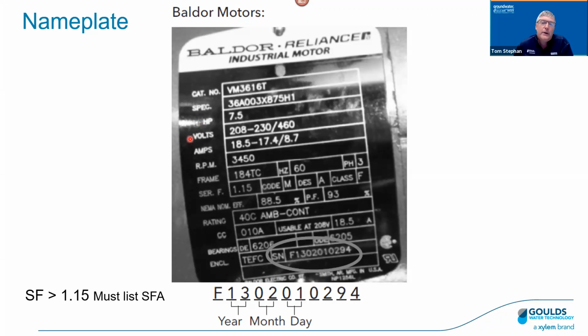And now we get into an area where there's always lots of questions and confusion. This particular motor, in terms of voltage, is a tri-volt motor. We can see here 208-230/460. Because there's a dash and a slash, that often leads to confusion. With this motor, this is a true tri-volt motor, so it can be operated with an input voltage of 208 or 230 or 460.